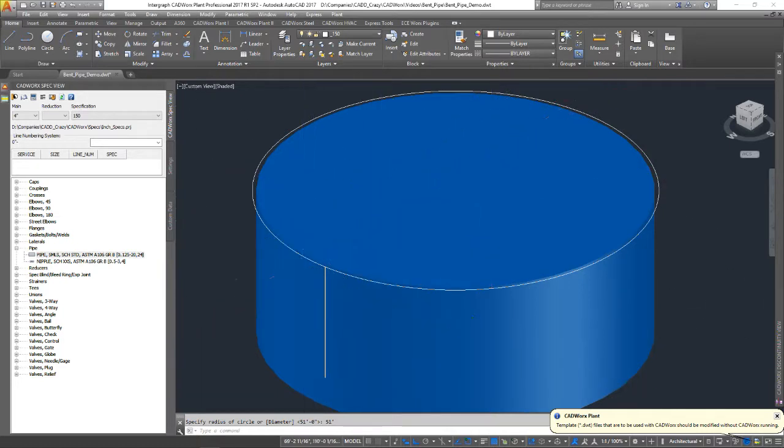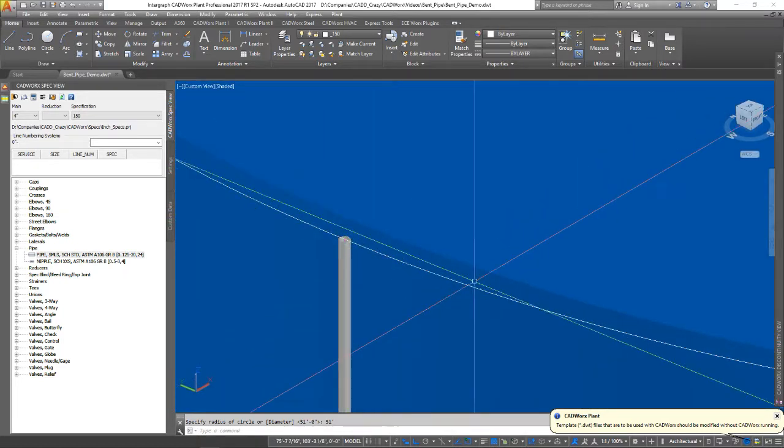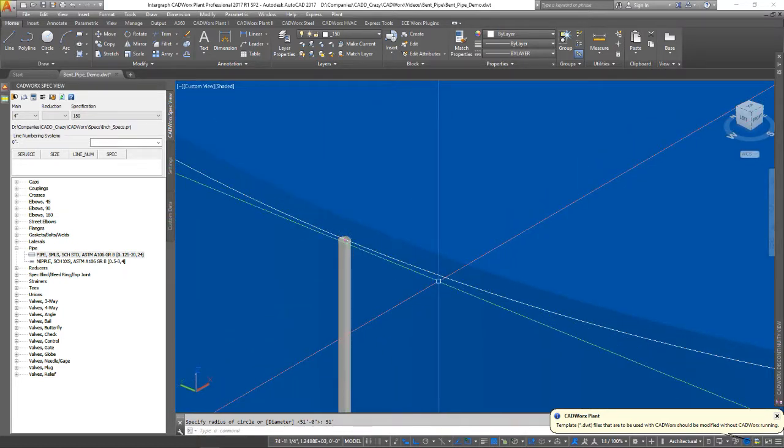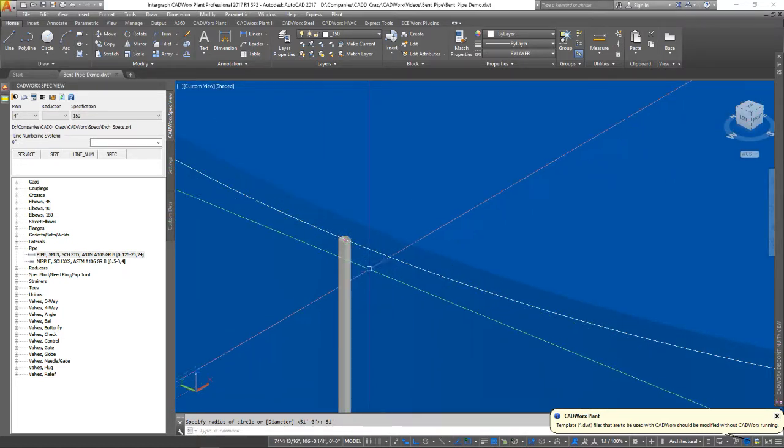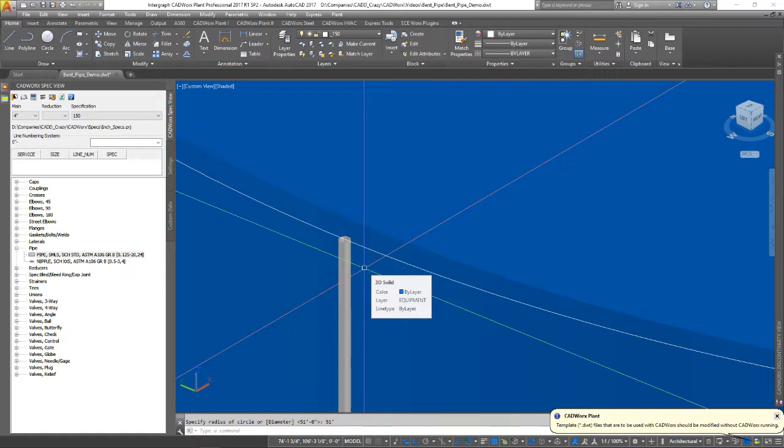Next thing you're going to have to do is you're going to have to break the circle because the command that we're going to be using does not use a circle. It uses an arc, a P line, to route that curved pipe, and AutoCAD does not look at a circle as an arc until it is broken.